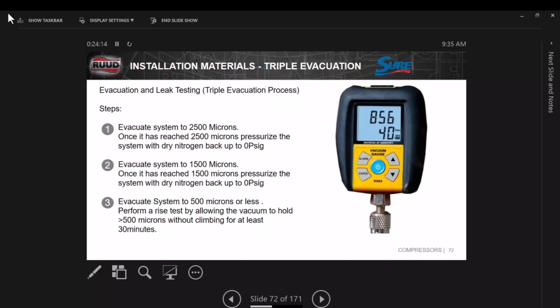And when you pull that copper line below atmospheric pressure, whatever moisture is in there is going to freeze. So when you start getting below the atmospheric pressure, we're going to start freezing that moisture in that system. And then when we put refrigerant in it, it goes back to water. Now we have water in our refrigerant. So how do we get it out of there?